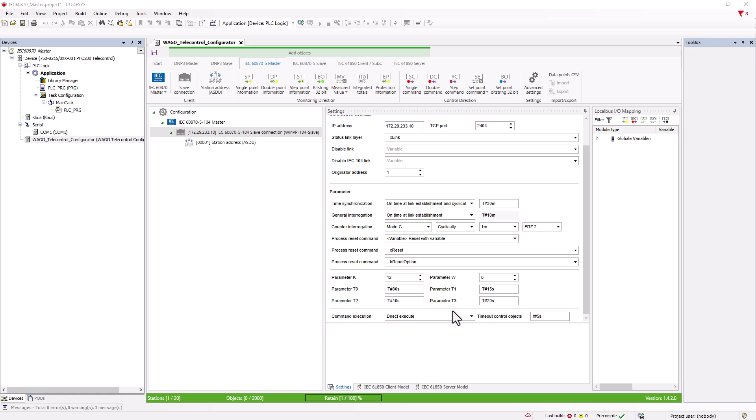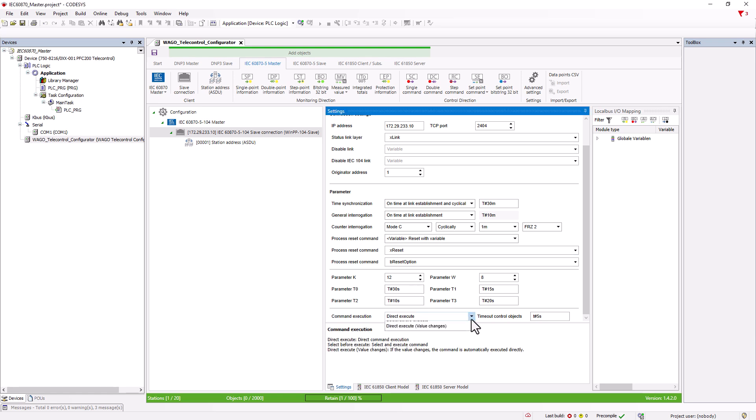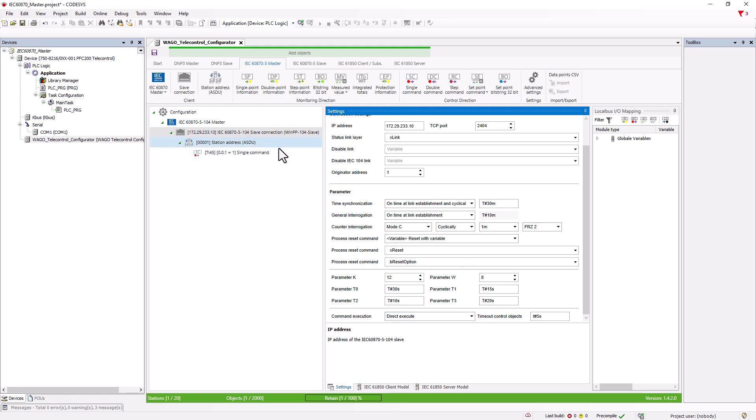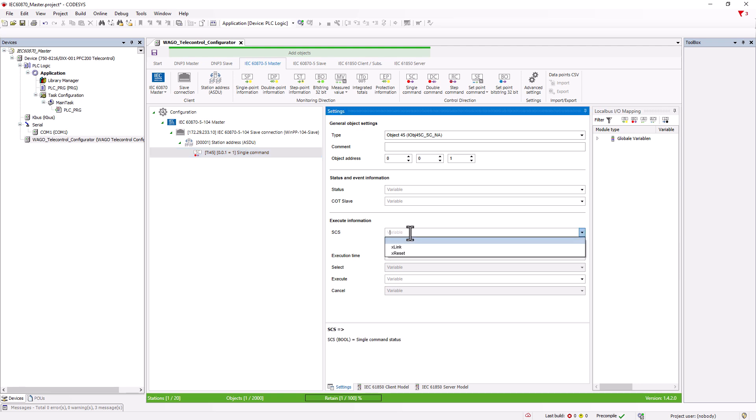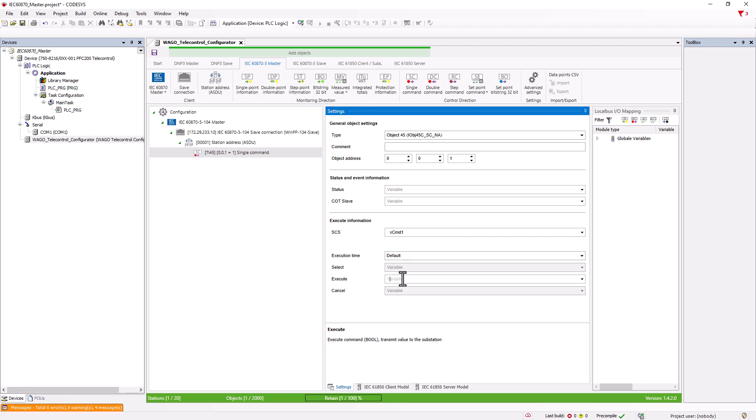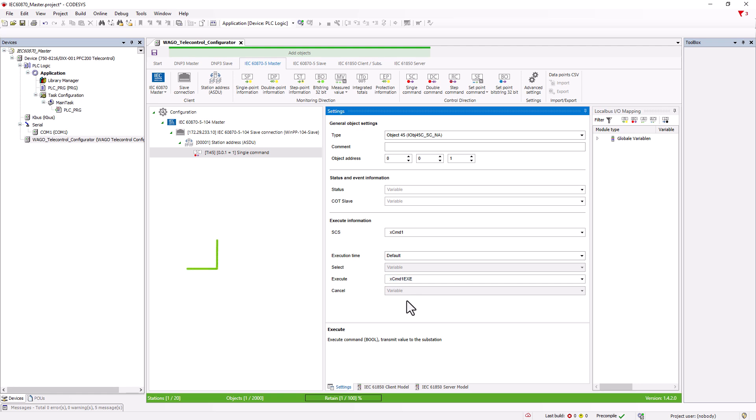At the bottom, you can configure how commands are to be executed. Firstly, whether commands are executed directly or whether a command has to be selected first. If we now insert a single command, we have the SCS field for the actual command value. The trigger variable for execution is specified in the field below. It is important to note that the positive edge of the variable is required for execution. A change from false to true must take place.